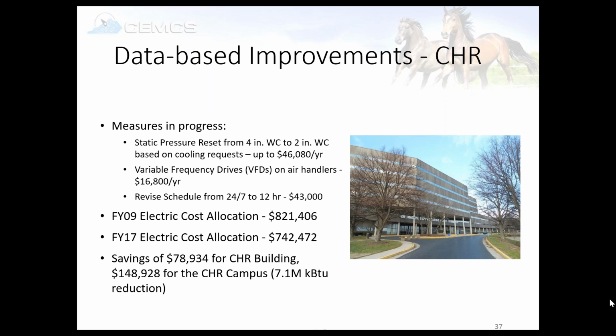We have 4 return fans, about 50 horsepower. We added VFDs to stage those on and off, whereas initially 3 supply fans were running at 80% 24/7. The next thing is revising the schedule from 24/7 down to a 12-hour day, 6 to 6.